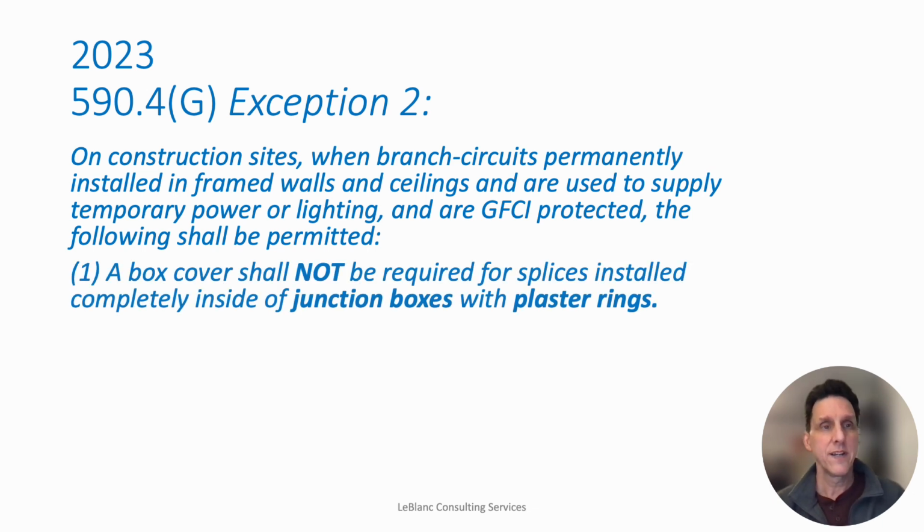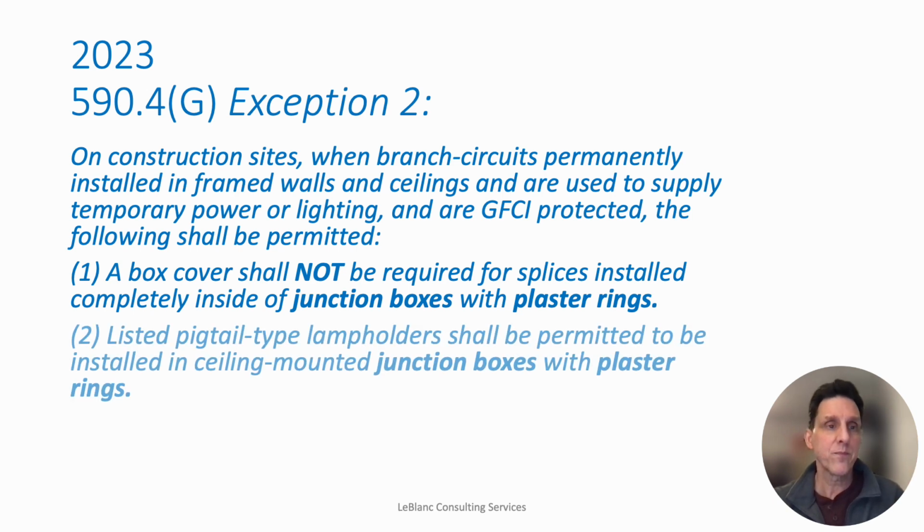Whoopsie. Number 1, a box cover is not required for splices installed completely inside of, it says, junction boxes with plaster rings, right? So it has to have a plaster ring, it has to be a junction box. That's what it says, right? But we want to pay attention to the specifics there and the nuances. Junction boxes with plaster rings. No cover needed if the splices are inside a junction box with a plaster ring, and you can energize that wiring for temporary purposes.